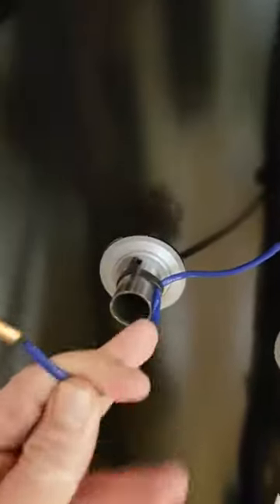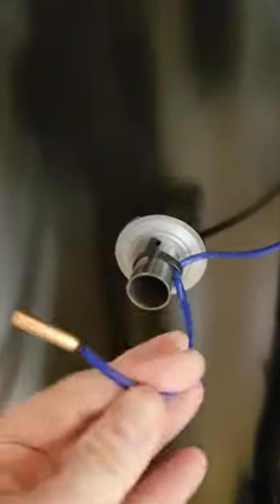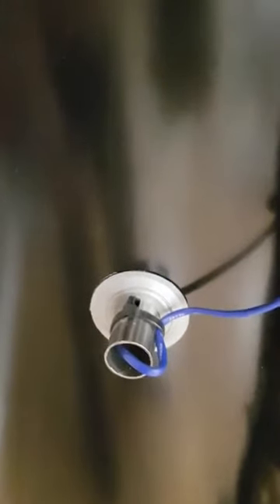The next important thing is the blue tank sensor. You can see it needs to go inside the tank at least about 100mm — right against the back wall of the cylinder. It shouldn't be able to go any further than this.